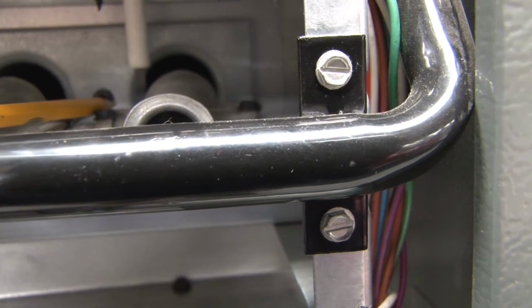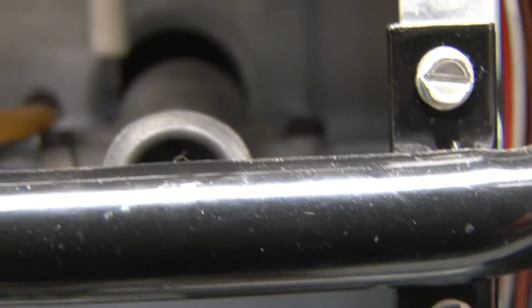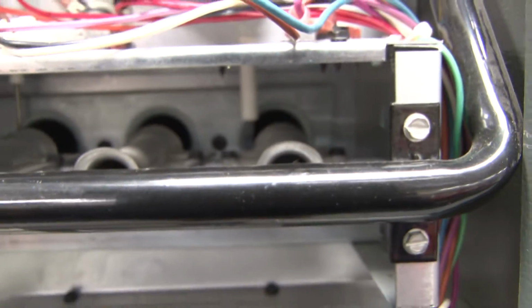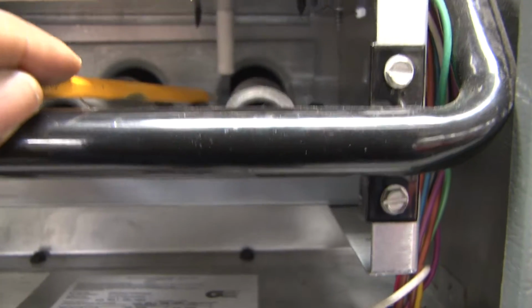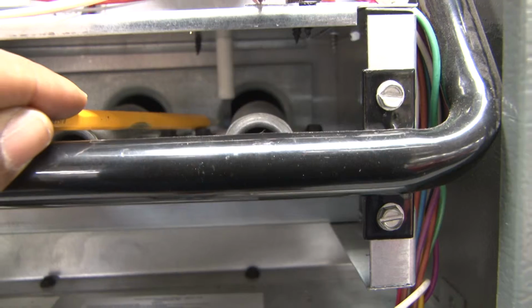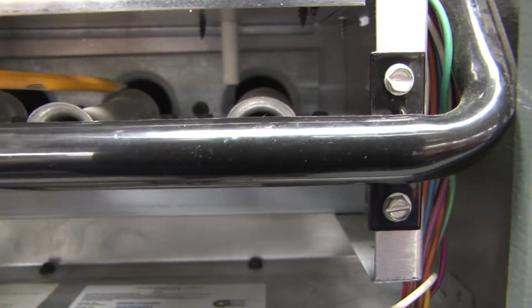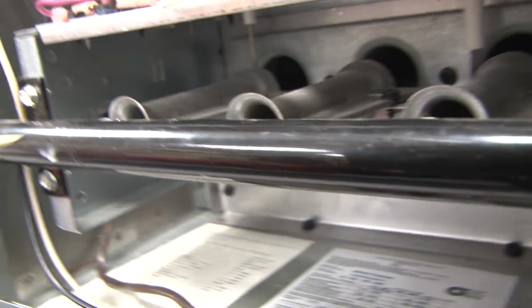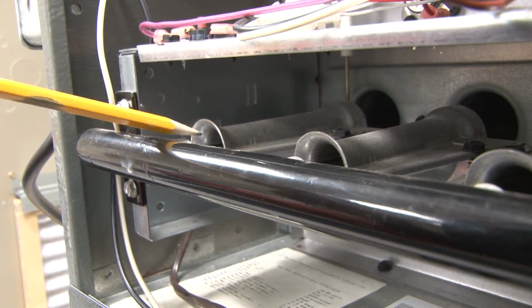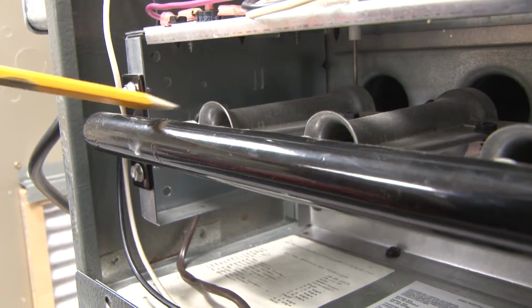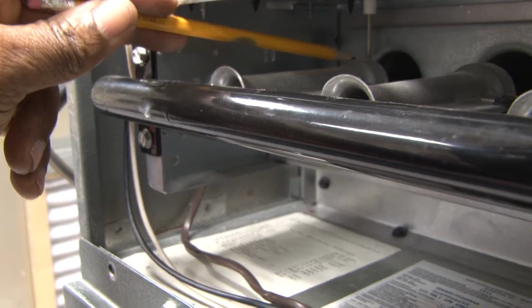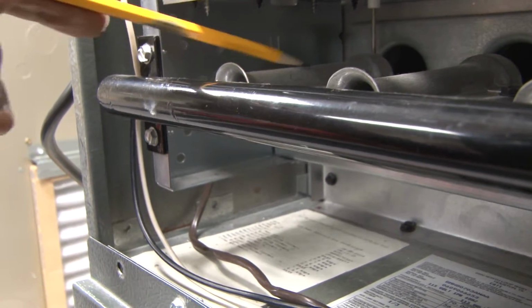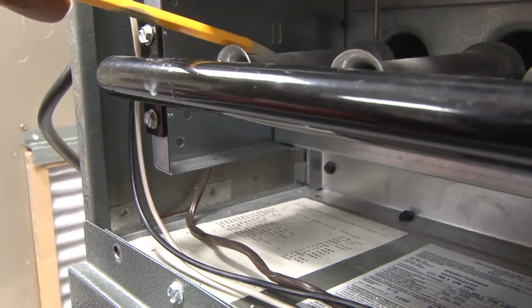I'll bring it in a little bit so we can see it better, maybe. That igniter, well, it won't focus, but you can see the igniter. It has a ceramic on it. It gets extremely hot, enough to ignite the fuel, which is natural gas. And as the fuel's mixing, we call that primary air. So it's pulling air to mix with the fuel to cause it to burn on the outlet of the burner. Not the inlet, it's mixing inside of the burner with air and fuel, which we call primary air.